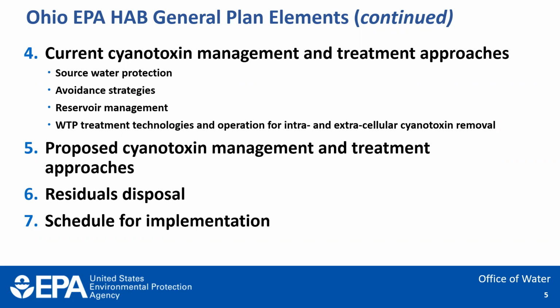Residuals disposal is important. I think Larry and Bill, during their treatment presentations, talked about sludge handling and your clarifiers. We showed that the settling process is pretty effective for removing the cyanobacteria cells, but then what happens when they're just sitting in the sludge? That probably needs to be processed more frequently than normal, in case those cells are still living and maybe releasing toxins. And so that's a consideration as well.